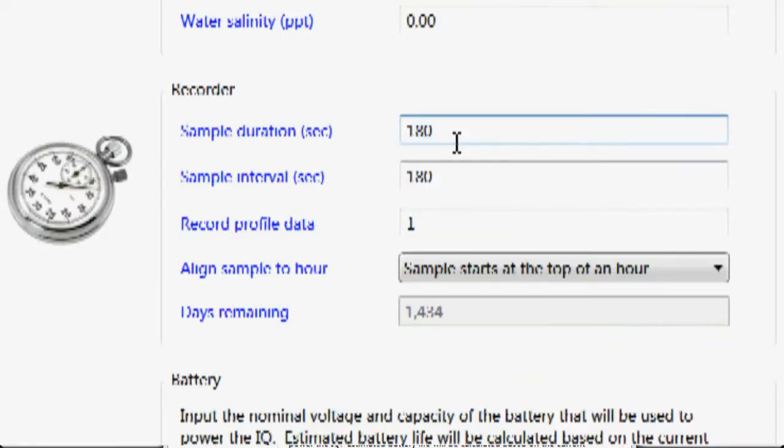Next we have the recorder. With the recorder, this is where we actually set up the instrument to collect data. We set first the sample duration, that is how long do we want to collect the data. In this case, we have it set up for 180 seconds, which is three minutes. The next thing we set is a sample interval. In this case, the sample interval is how often we want to collect that data. It's also set to 180 seconds. When I have this type of setting, the instrument will actually literally run continuously.